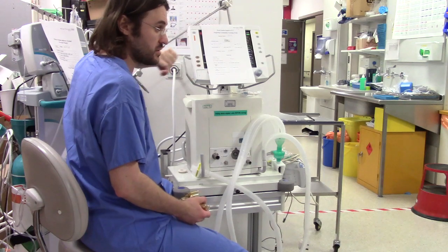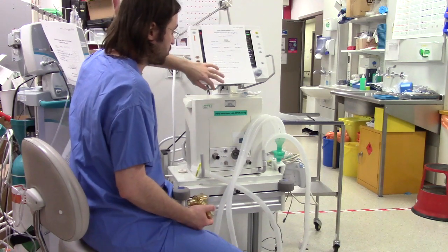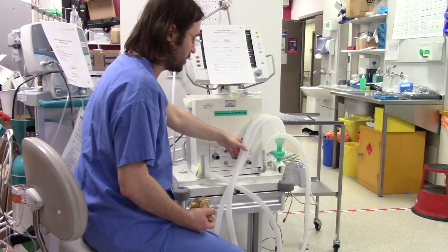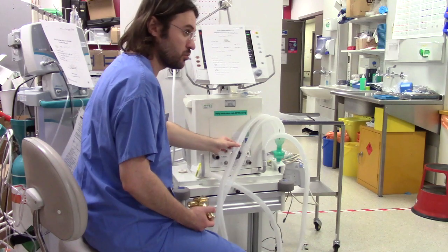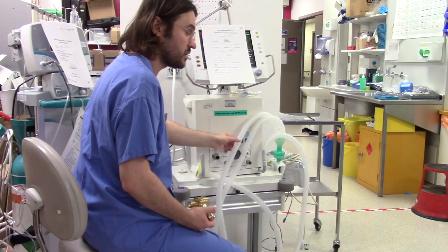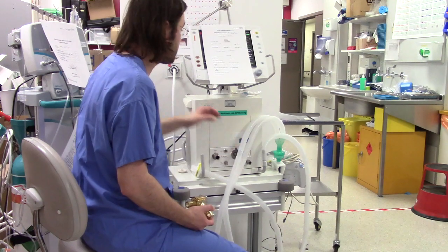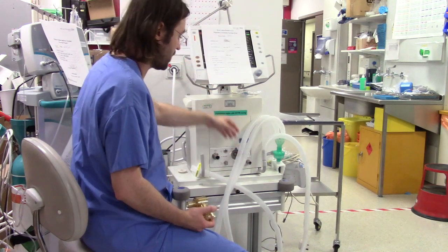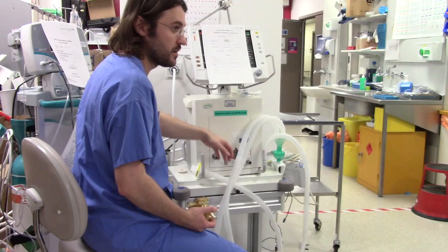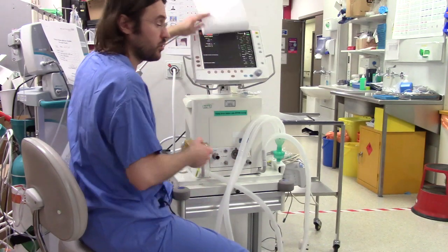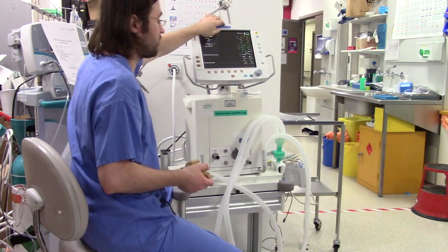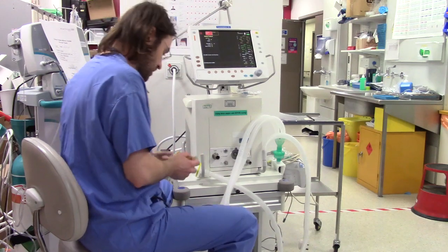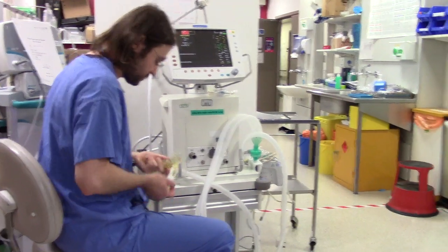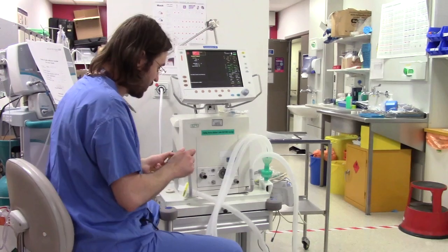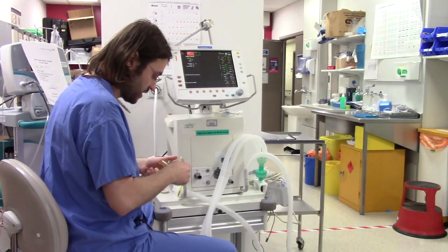But still, it is recommended that before you connect it to the patient, you do a pre-use check, because obviously you'll be using it with a new circuit, and sometimes there is a very, very small chance that the circuits may come damaged from the supplier, and you can find that fault by doing this pre-use check. So about the block, yeah. We assemble the block here and we do the pre-use check.